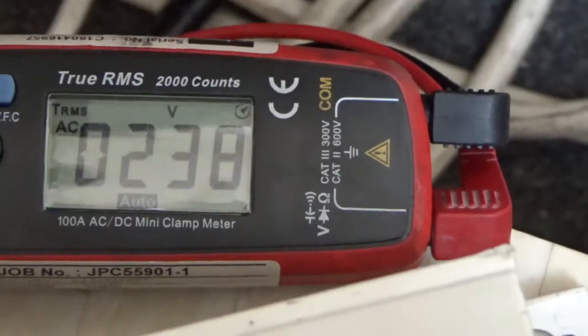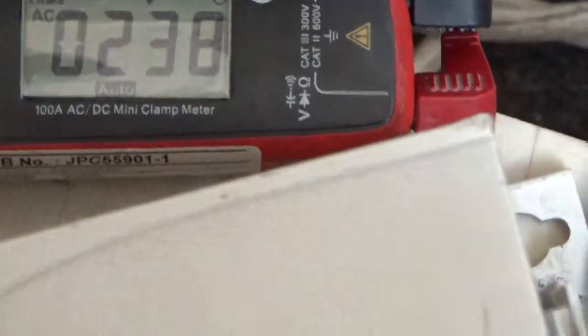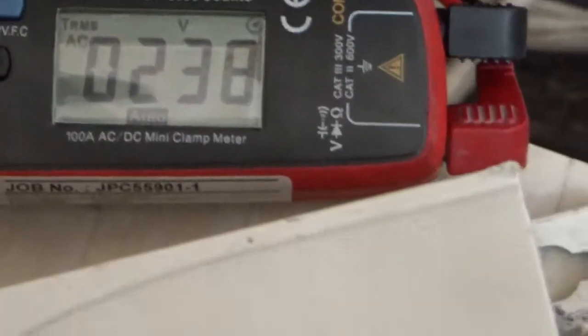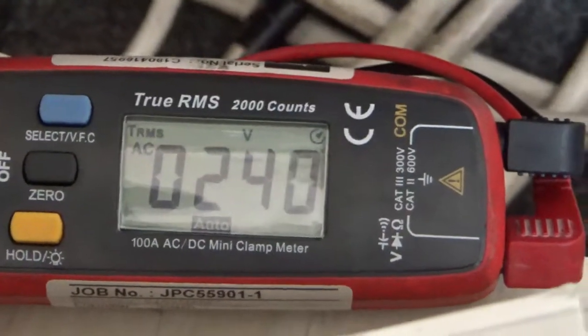238. Now if you do phase to earth on that, see what happens. Put one on earth. It's still showing the same, so there's no issues on that side.